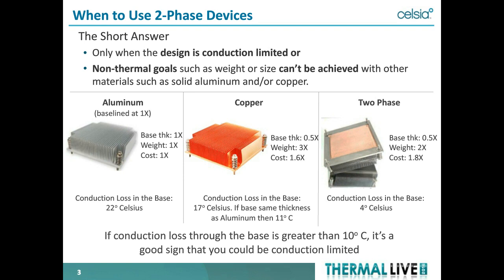We have three examples comparing the same application, same heat sink format, same airflow, same power. An aluminum heat sink, a copper heat sink, and a heat sink with a vapor chamber embedded in the base. For aluminum, the delta T due to conduction in the base is about 22 degrees. Going to copper and keeping the same base thickness cuts it in half to 11 degrees, though often thinning the base gives 17 degrees. But with a two-phase device, the conduction loss is only 4 degrees — that's why you'd go to two-phase.